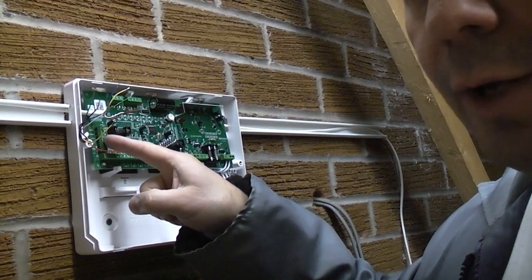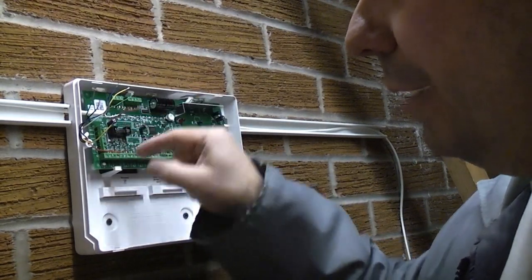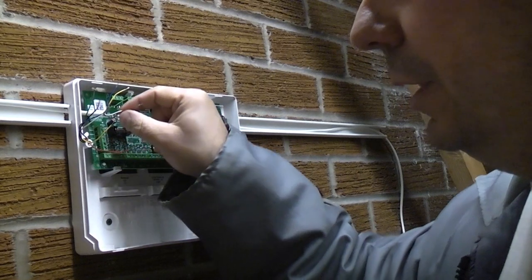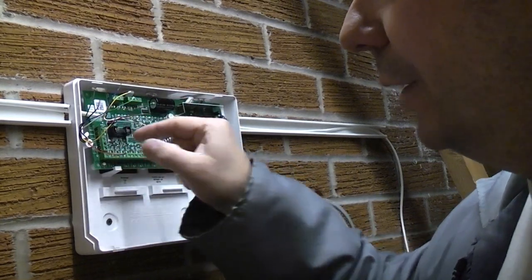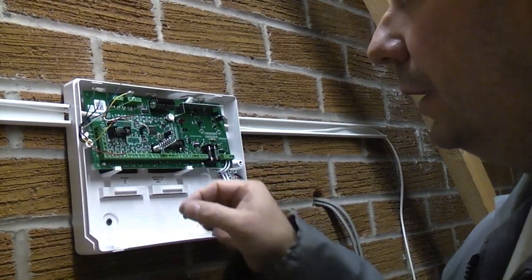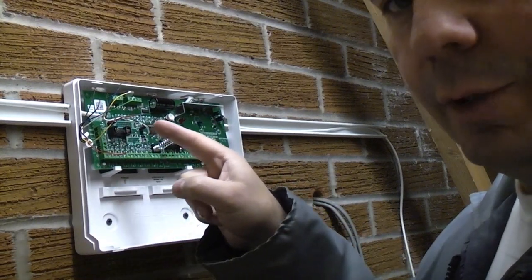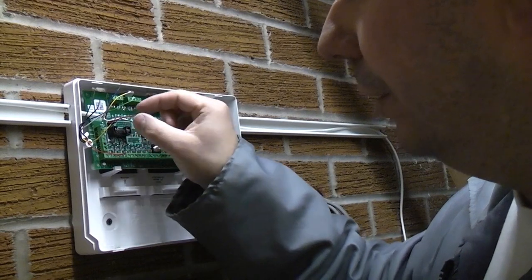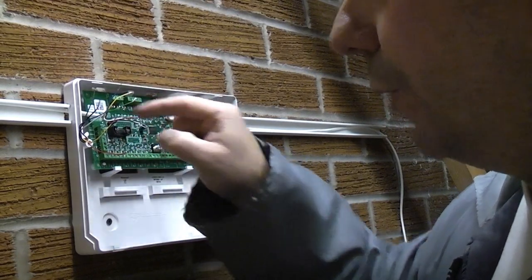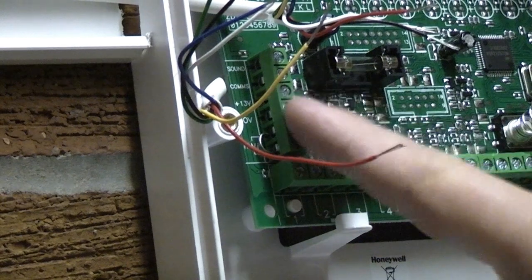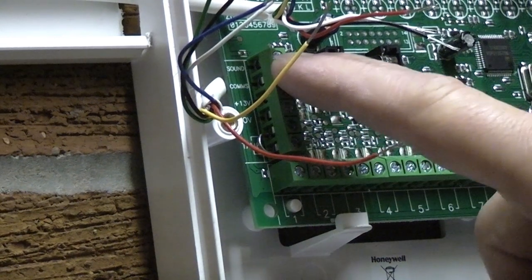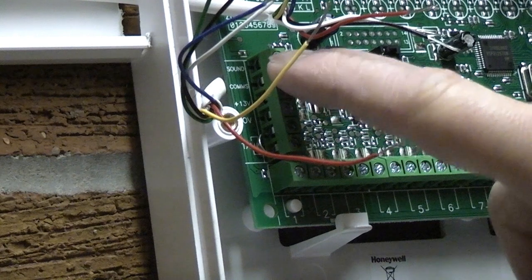On a lot of alarms you may only have one keypad, so you will only have one cable with one set of wires. On this particular alarm we're going to have two keypads, so we're going to wire the two keypads into this terminal. You'll notice that I've stripped the wires already and we've got about 15mm of conductor showing on each wire. The top terminal on this is the sound which is the blue wire, so we're going to get the two blue wires and twist them together.